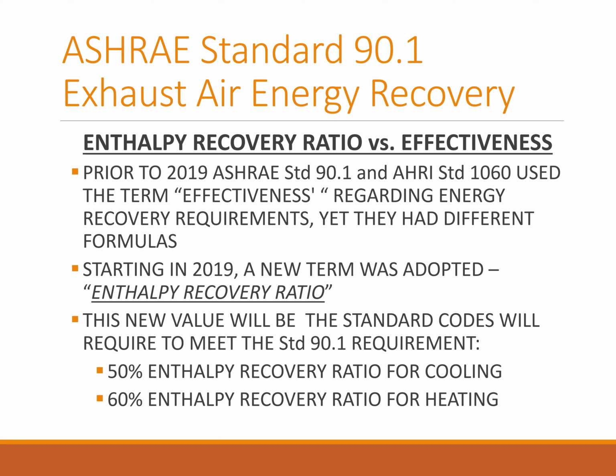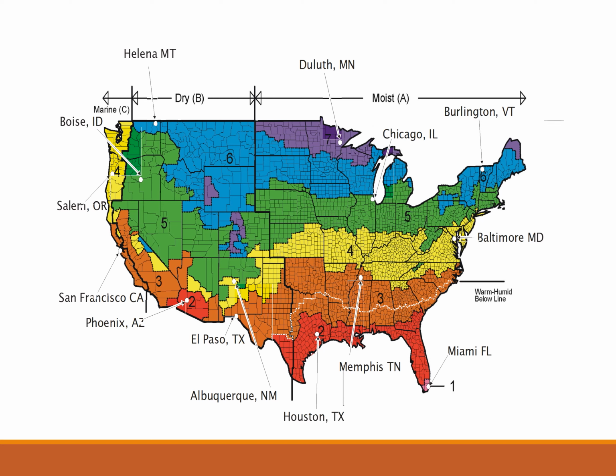This is a weather zone map of the United States. When talking about energy recovery requirements, there are temperature zones 1 through 8 and humidity zones A, B, and C. Each city in the United States in a zone will have both a number and a letter. For example, Indianapolis is Zone 5A.